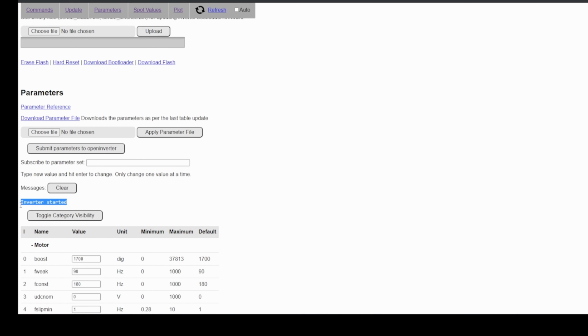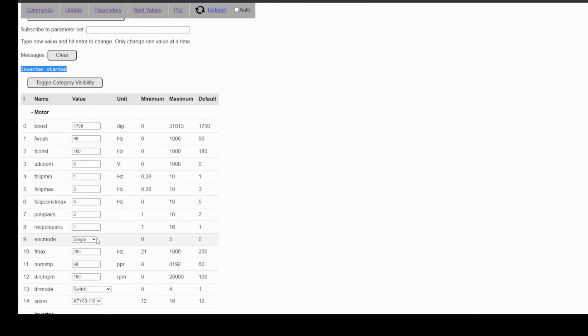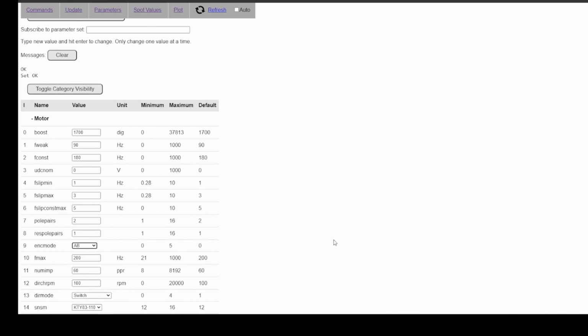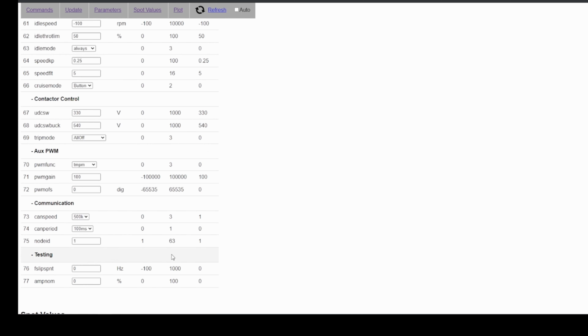Now I'm starting the open inverter console and selecting AB, which basically means no encoder, and going to the testing section, where I will set ampnom to 100 and F slip to 10. And we are spinning. We can rotate the motor in sine mode.